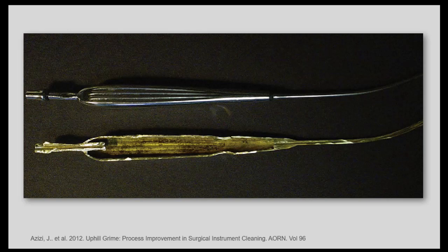And we'll come back to that publication a little bit later. But I really want you to look nice and clearly, so I'm going to use this red dot pointer, is what it looks like inside a suction. If you take a brush and you pop it in this lumen over here, you're going to have a brush size that can fit through that lumen, but it's not going to be big enough to clean the whole inner aspect. And that lumen is still bigger than the front of the device, which is going to be a hell of a lot smaller. So no matter which way you shove a brush in here, you're never going to clean the entire cavity of a Yankauer sucker. Not with a brush. It's just physically impossible. The design of the instrument does not allow that.